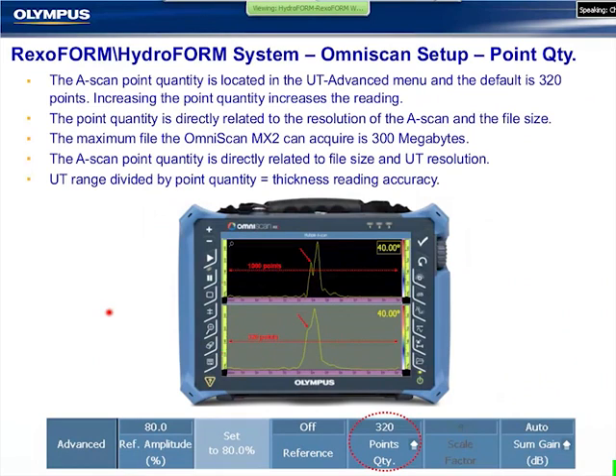In the OmniScan setup, you'll also find the point quantity. This is normally set to 320 by default, and for the weld inspection it is not so critical because the use of A-scan compression allows us to retain amplitude while reducing the resolution in the time axis. So if our procedure requires a 0.1 millimeter thickness reading, I need to ensure that my range divided by the number of points is at least what the minimum thickness requirement for the procedure is.